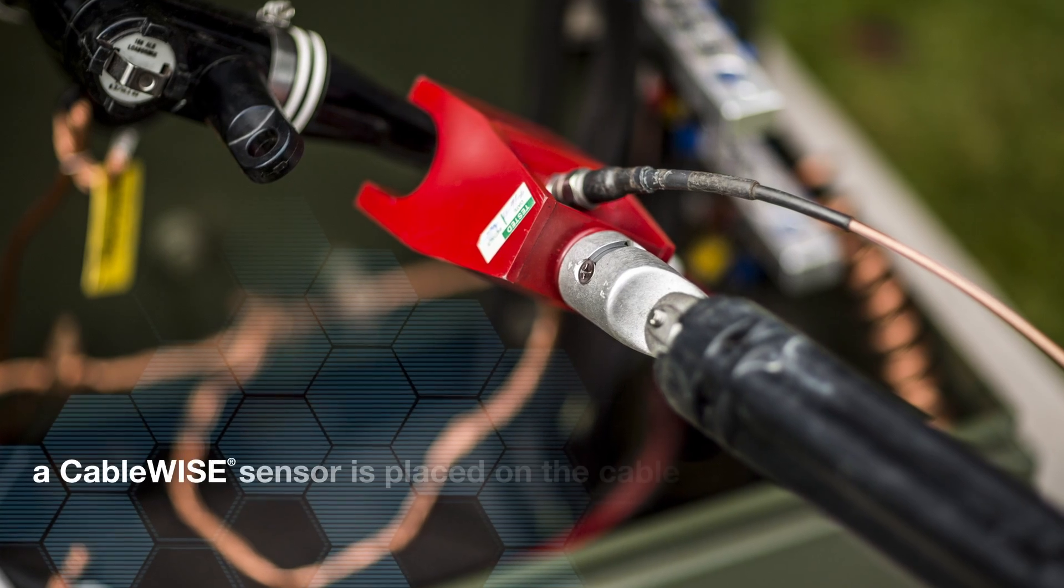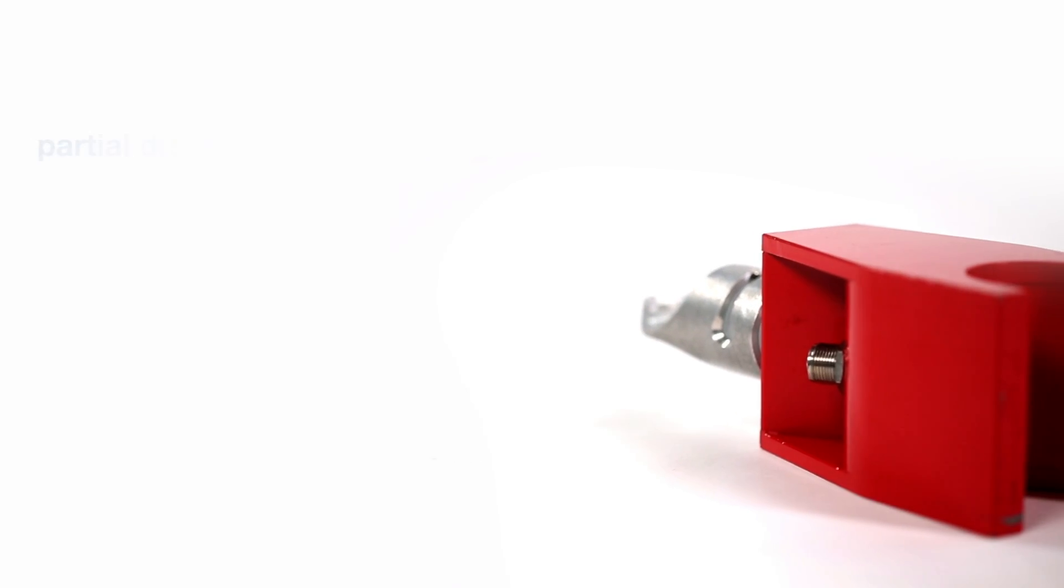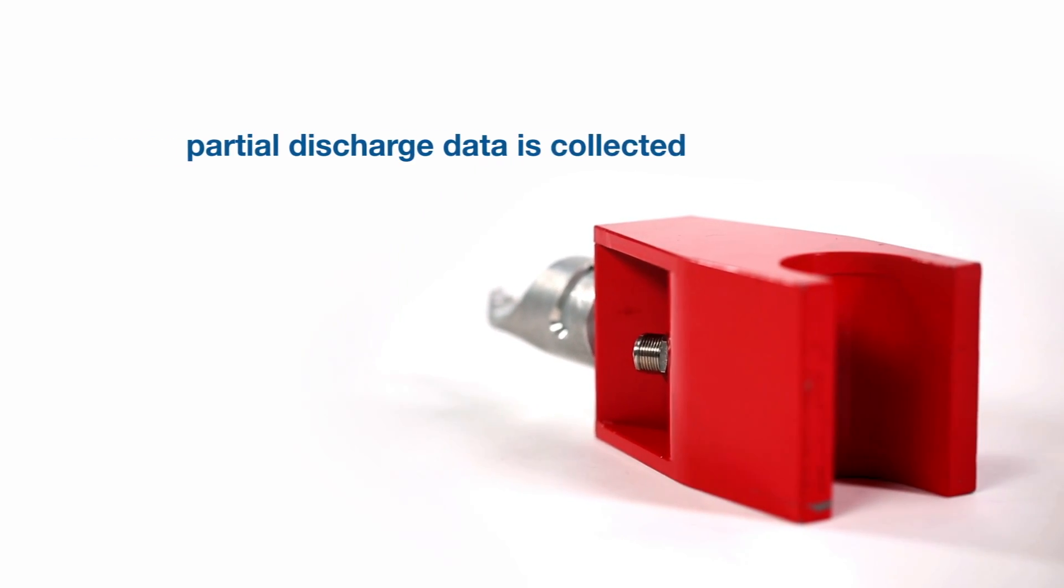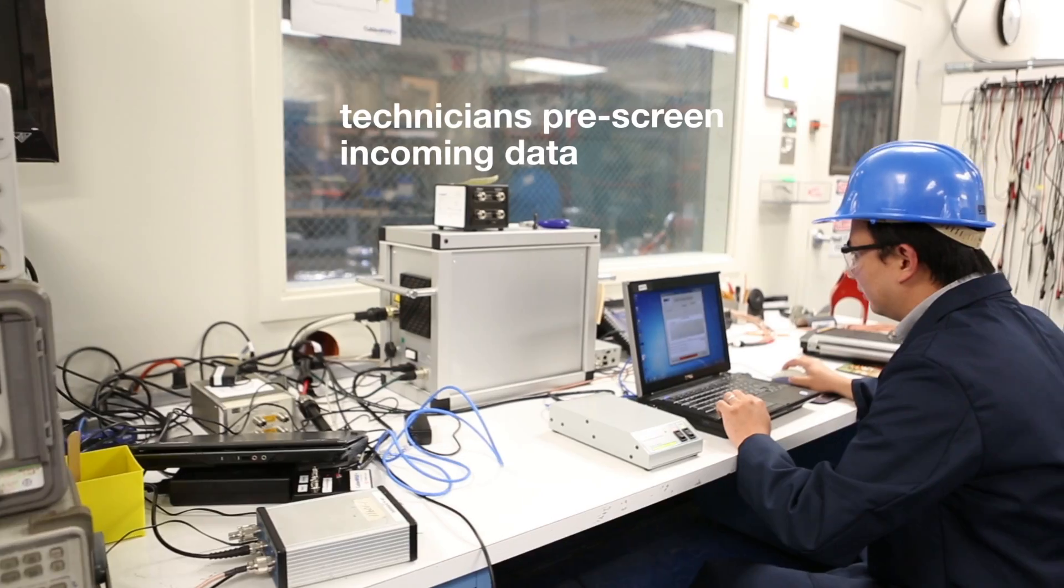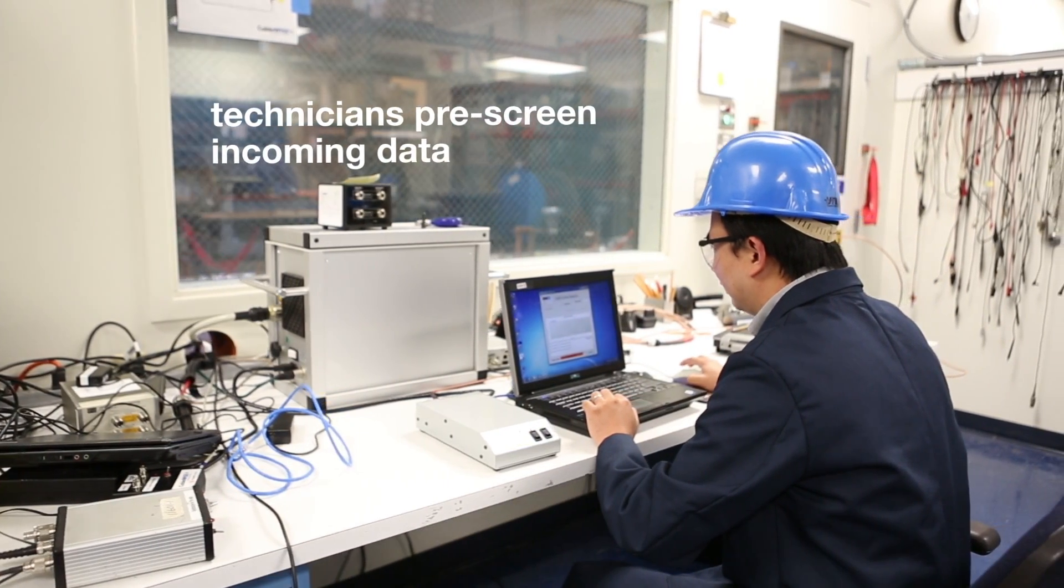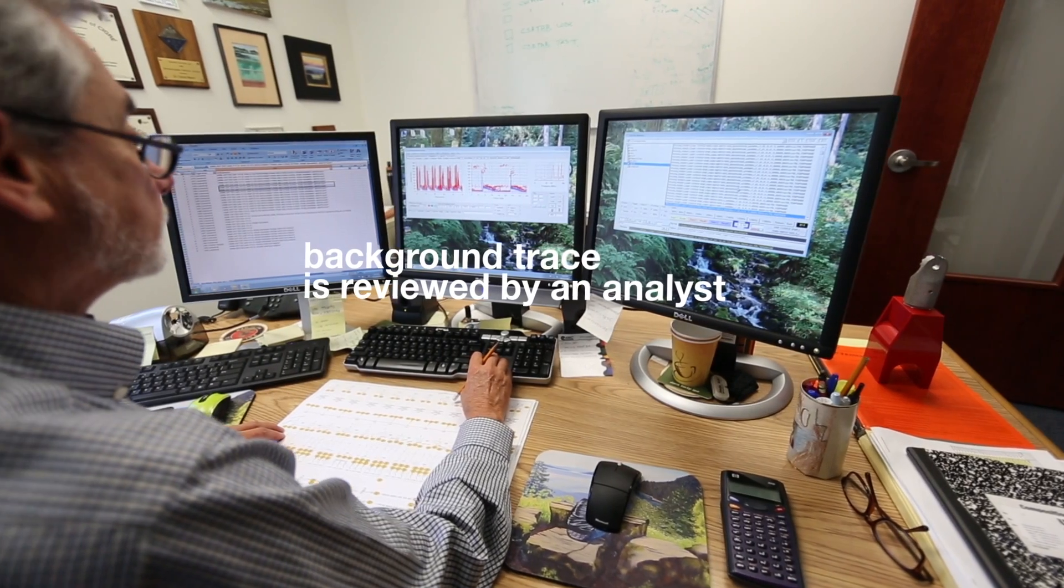A Cablewise sensor is placed on the cable near the termination, and partial discharge data is collected for several minutes. Technicians pre-screen the incoming data and record a background trace, which is then reviewed by an analyst.